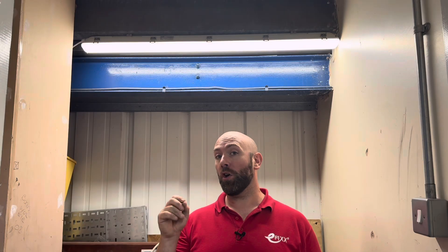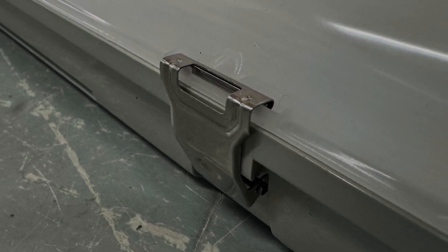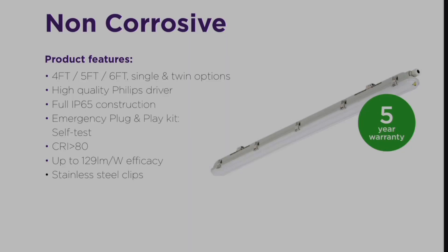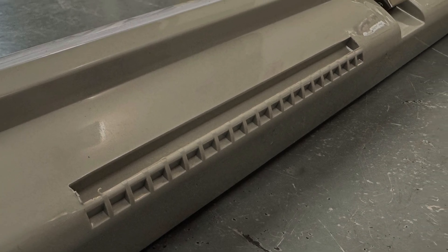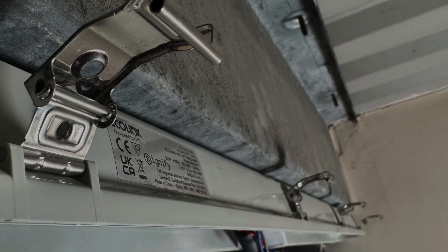Now we come to Ecolink's take on a non-corrosive LED fitting. This is a really sleek fitting which comes with a high-quality Philips driver. It's fully IP65 and has optional emergency packs available. You can use the same battery pack used earlier in the batten fitting. With the five-year warranty as standard, this fitting is going to stand up to the most arduous of locations. The NCF fitting is available in four, five, and six-foot, with single and twin options. The clips let you mount it without needing to be too exact — get the clips in and the fitting just drops into place. Two stainless steel clips lock in, so when you unclick the LED tray it will just hang there. All the clips stay in the open position, making it even easier to put back.